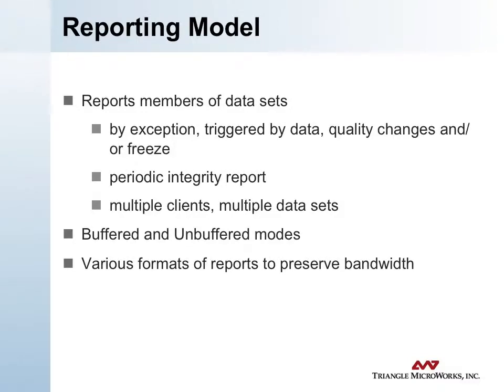The 61850 reporting model can be pretty complicated. You essentially report members of a data set by exception — only the changed values are sent in any given report message. The exceptions can be triggered either by data or quality changes or freeze updates for counters. There's also a periodic integrity report, multiple clients, multiple data sets, so you can have the same data going to different clients at different times within different data sets. There's a buffered and unbuffered mode, and various formats of reports to save on bandwidth and make things simpler for the client. The model is a little bit complicated; I'll go into more detail in the next slide.